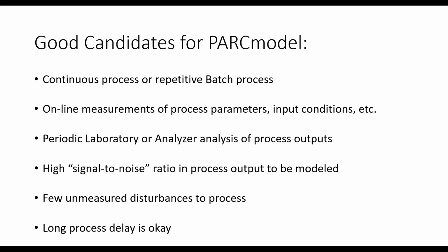Another thing to look for is parameters where the output parameter especially has a high, what I call signal to noise ratio. So we don't want a lot of random variability in the output parameter analysis, at least compared to the real variability, the longer term trends that you see in real changes in the process. Because obviously we can't model random noise. It's unpredictable. So we need signals that are relatively clean. They don't have to be perfect, but the cleaner the better.